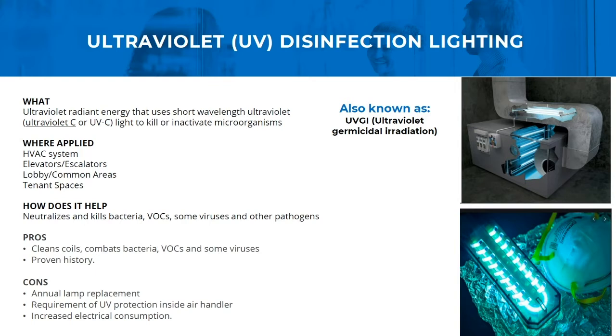The pros too is it's been around for close to 50 years. It cleans coils and air handlers very well. Combats the bacteria and the VOCs and some viruses. The cons that we have with UVC is annual maintenance. So there's lamp replacement that you need to do annually. There's also the requirement for protecting the inside of your air handler or any device that it's in, being that UV is technically the sun, it deteriorates plastics fast. So anything within your air handler needs to be protected. And then your electrical consumption obviously will go up. So those are just a few of the cons and pros that we have with UV lighting technology.